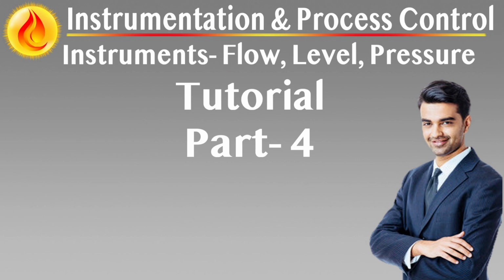Electrical and signal integration. Turbine meters provide pulse output, often with magnetic or optical pickups. Signal conditioners or amplifiers must be mounted close to the meter to preserve signal quality, especially in hazardous or noisy environments. Pulse signals can be scaled for totalizing, batching, or flow rate indication, and are easily integrated into PLCs or flow computers. Installation and support requirements. Install meters horizontally with the rotor axis aligned with flow direction. In liquid service, ensure meter is always full and air is vented during startup. In gas service, install upstream filters and automatic air eliminators to protect rotor stability.